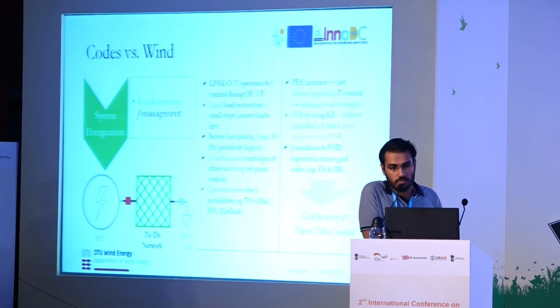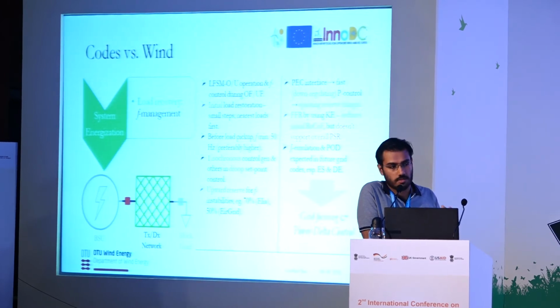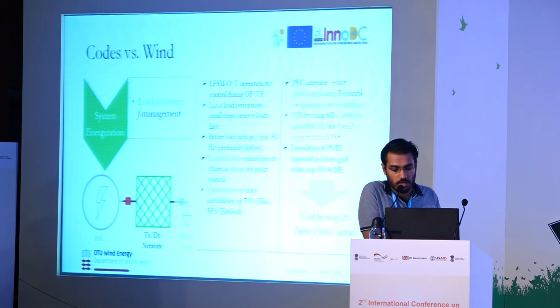For frequency control, load pickup is used during the restoration process, as I mentioned earlier, and it is the priority loads that are picked up first in small steps, with a minimum requirement that frequency be a bit over 50 hertz, so that when the load is picked up, it doesn't go to another frequency instability point. However, upward reserve is very important during the initial stages of the power system restoration to deal with fluctuations in the offtake of reconnecting grid users. And different numbers are there from different transmission system operators based on their network capacities.